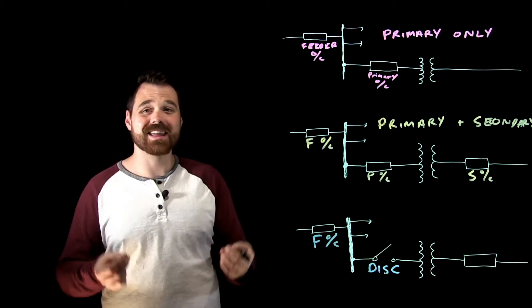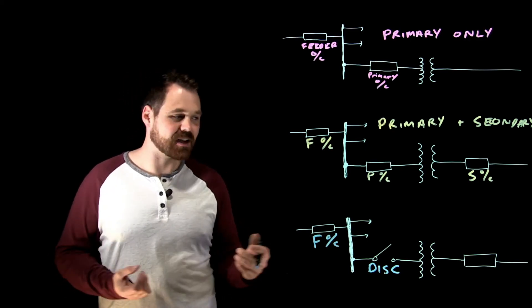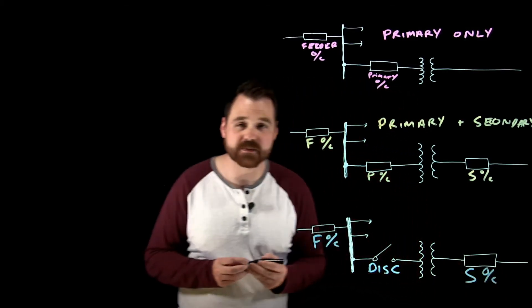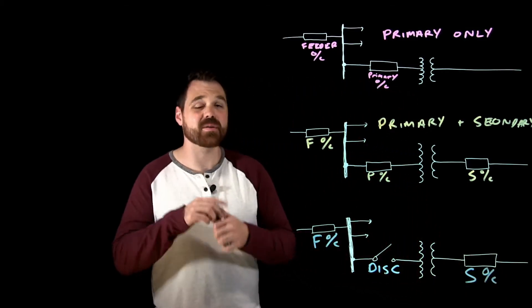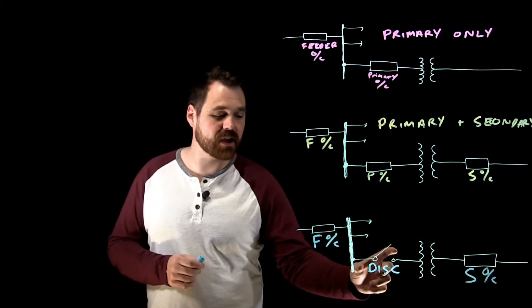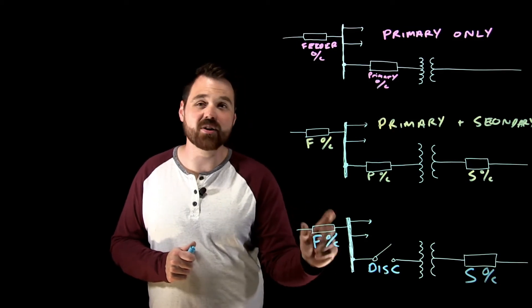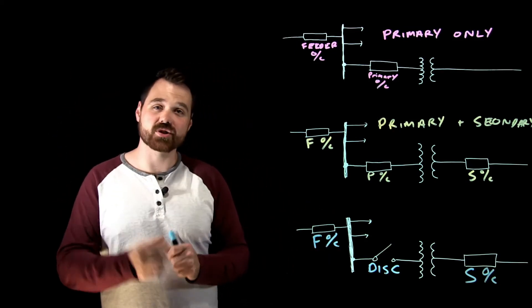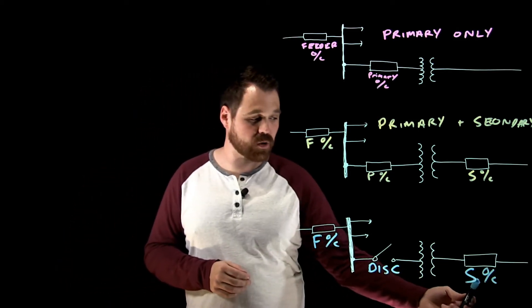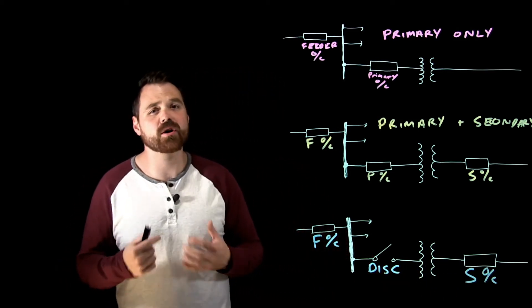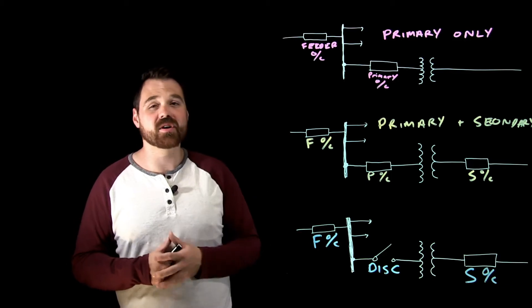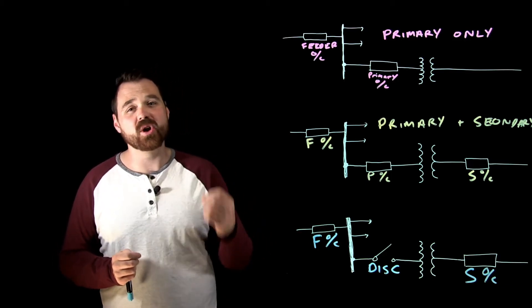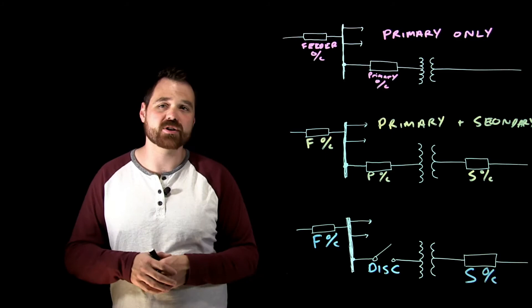What happens in that situation is I am going to require that secondary overcurrent device. The reason is that because I only have a disconnect on the primary, my feeder overcurrent is so big that it's only going to protect against short circuit conditions. So I am going to require that secondary overcurrent device, and that secondary overcurrent device is really there to provide overload protection so we're not burning out the transformer.